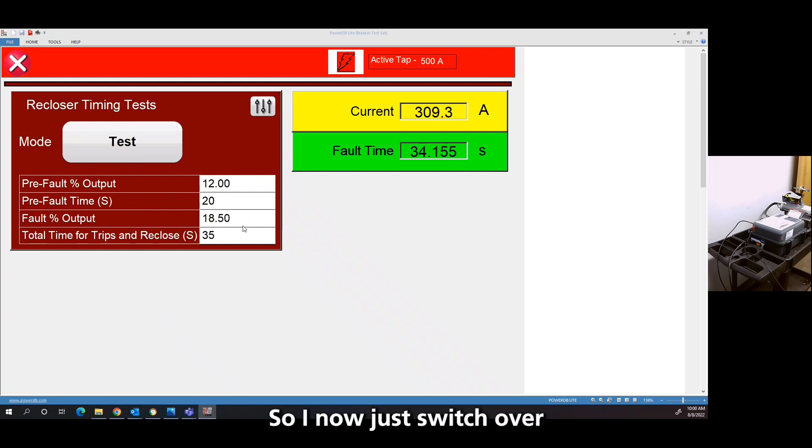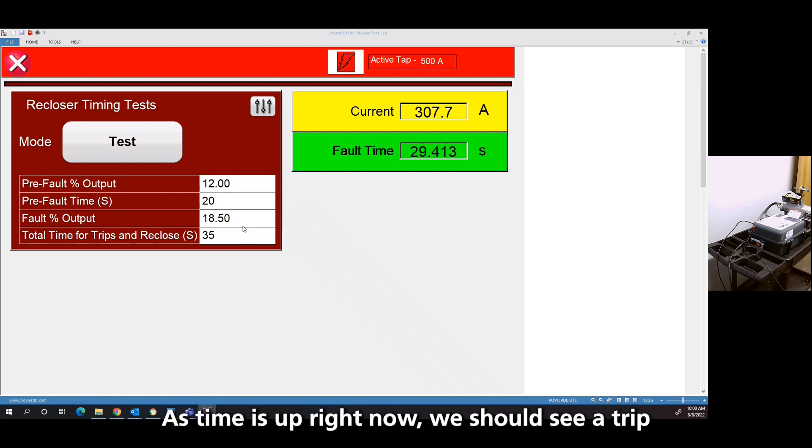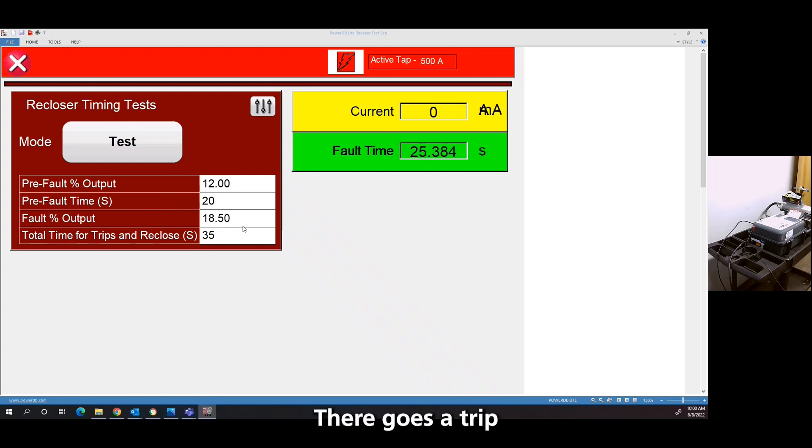it'll switch to the 18.5%, which we know is 300 amps. So now I just switched over. Once again, these are pretty long curves on the first one. It's timing out right now. We should see a trip. There goes the trip.